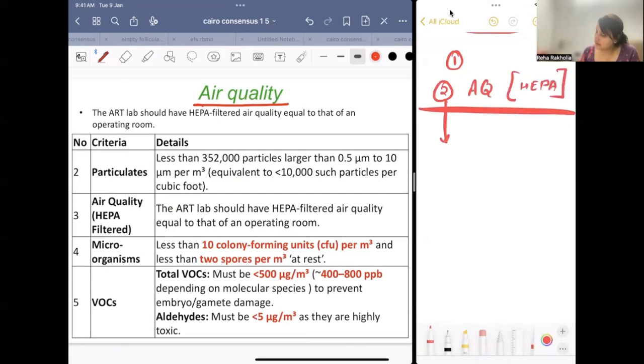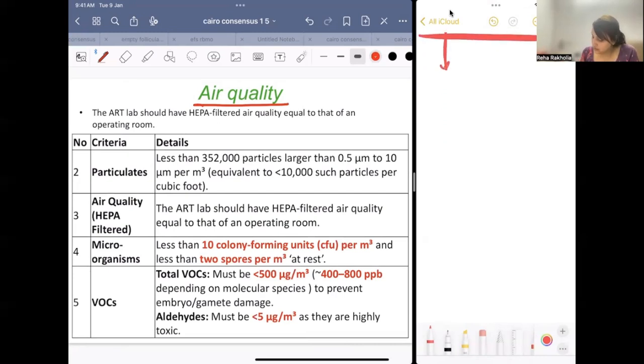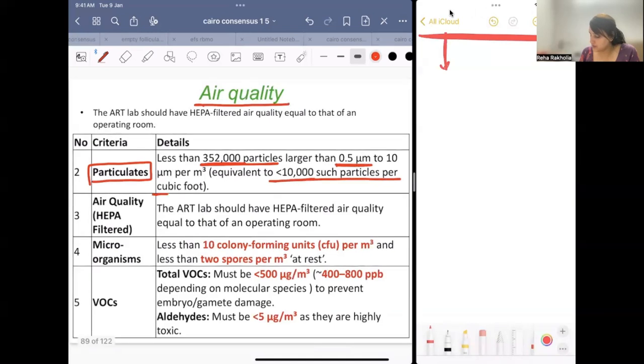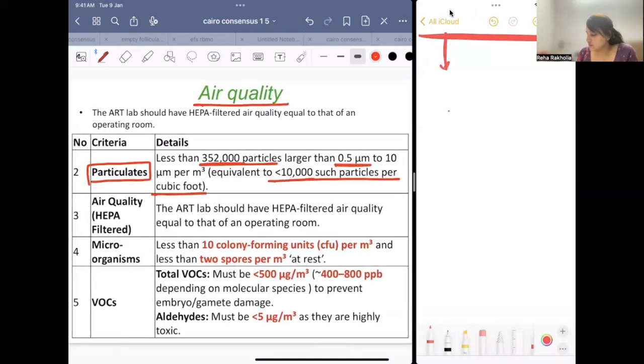Now about particulates - they should be less than 3,52,000 particles larger than 0.5 micrometer, equal to or less than 10,000 such particles per cubic foot. Note that 1 meter cube equals 35.3 cubic feet.